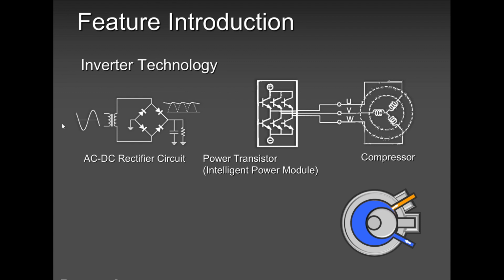So your AC power comes in, your AC single phase comes in, goes into this rectifier circuit, converts it to DC volts. It gets into this IPM module. The IPM module is responsible for converting from DC to AC. And this UVW is your three-phase driving that compressor. And that three-phase is AC, not DC.